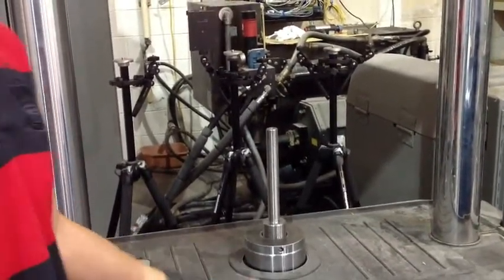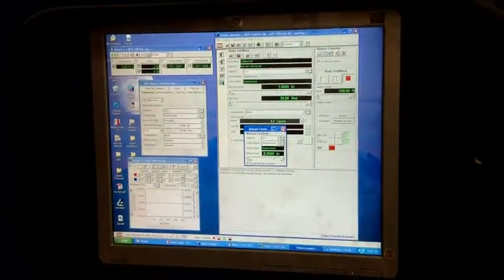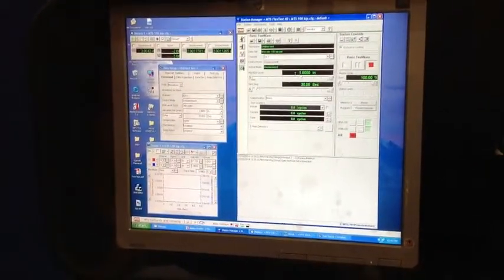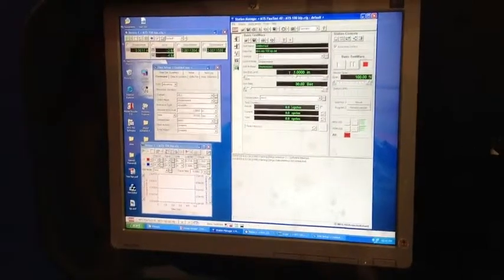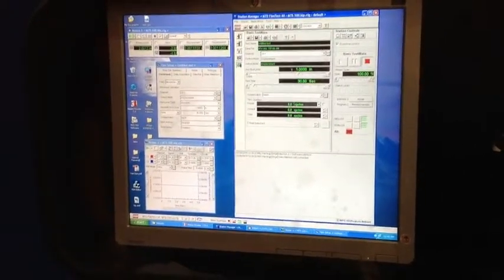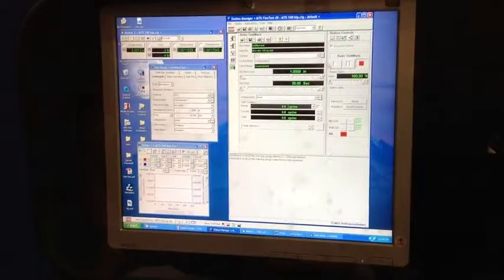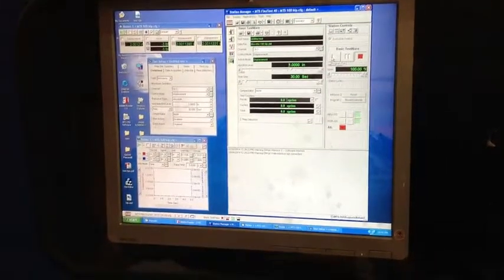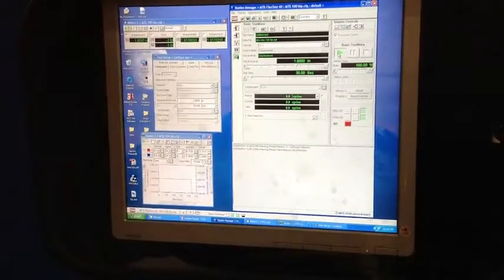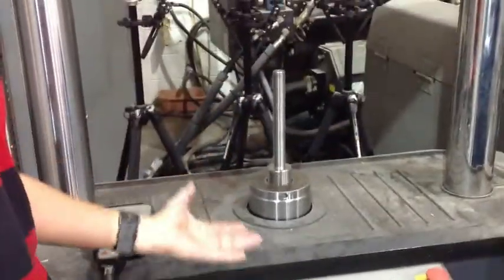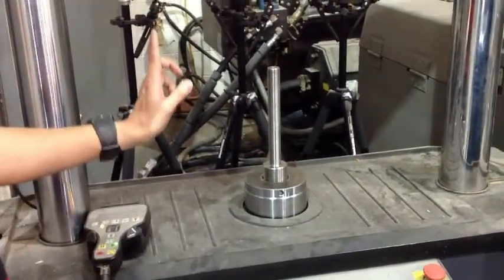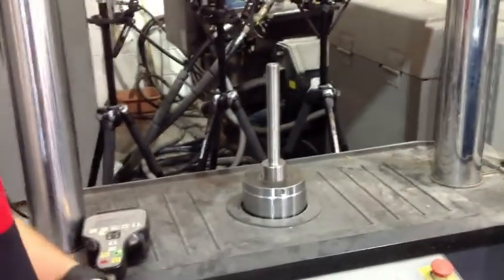So after displacement was set, you close this window. And double check what we have in here. And so like I said, we want a 1-inch displacement within 30 seconds. We are all set in here. Then you will need to click on program run. Then in the actuator part, even if you cannot see, the actuator will be going up for 1 inch within 30 seconds.